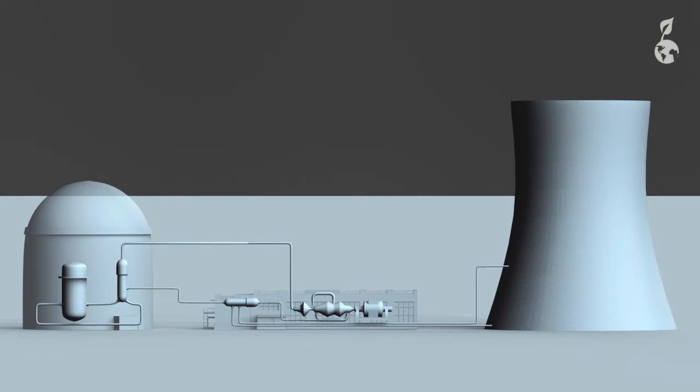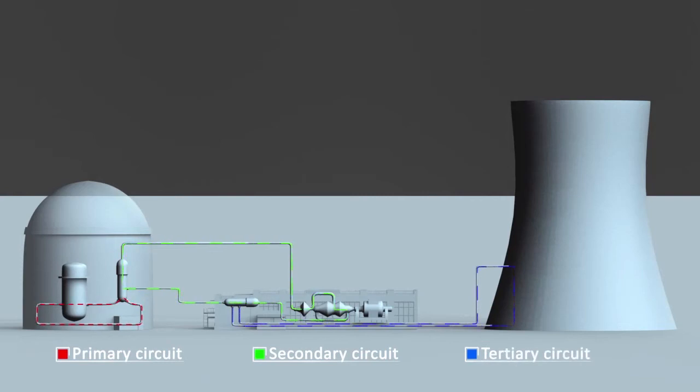Water in the primary circulation system never leaves the containment building. This water is radioactive since it has been in direct contact with the fuel rods. Water in the secondary circulation system is used to drive the turbines and is not radioactive. The cooling circulation system provides cool water and is used to condense the steam in the secondary circulation system.